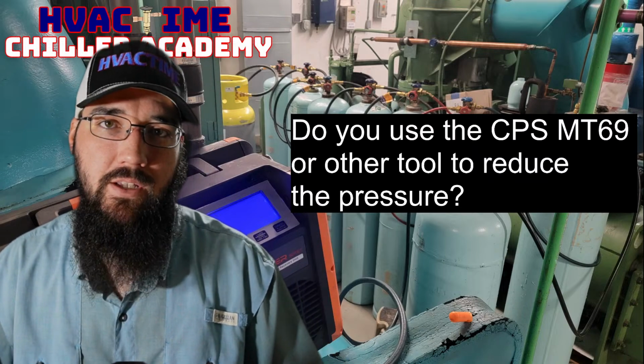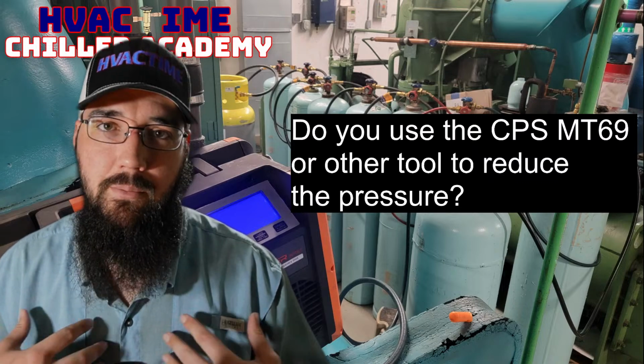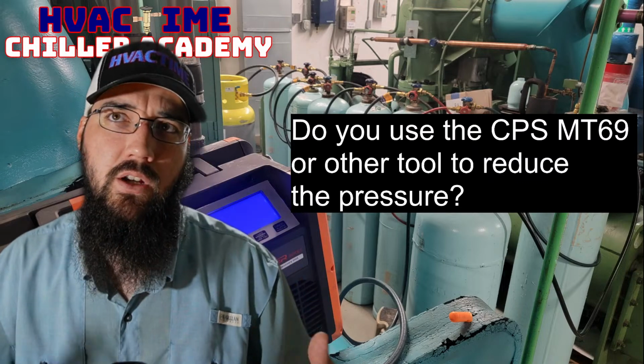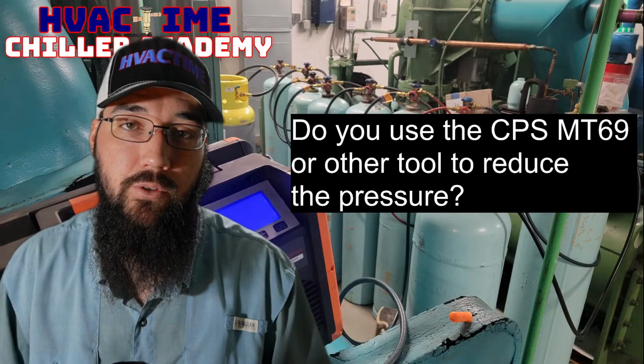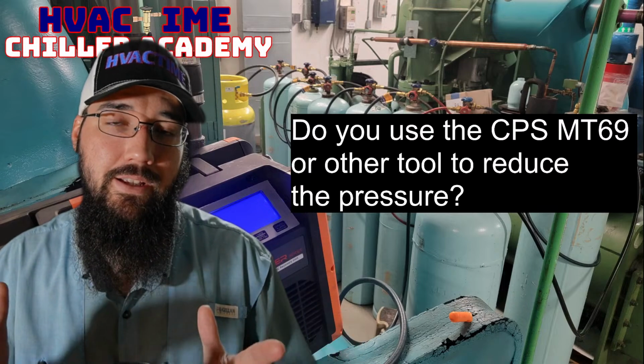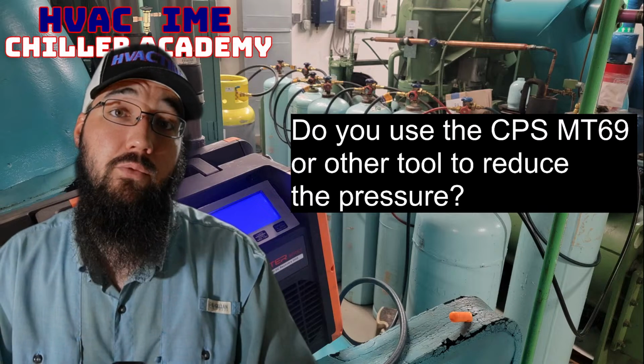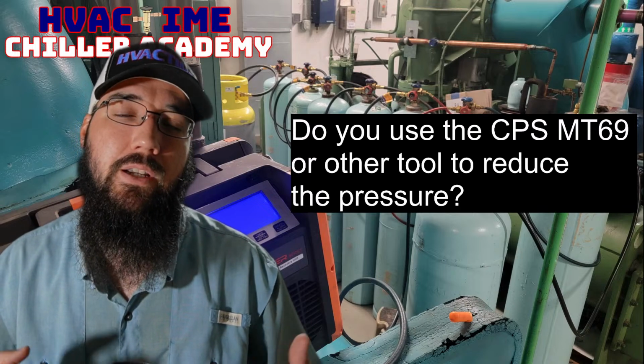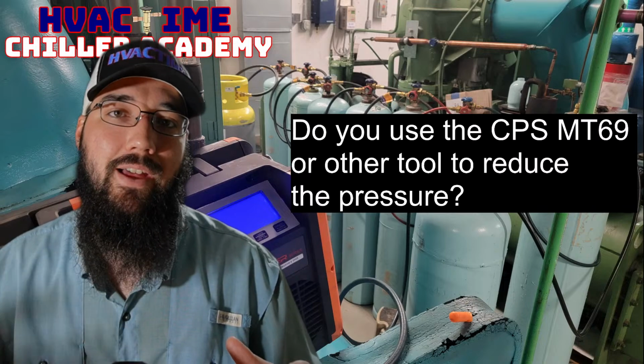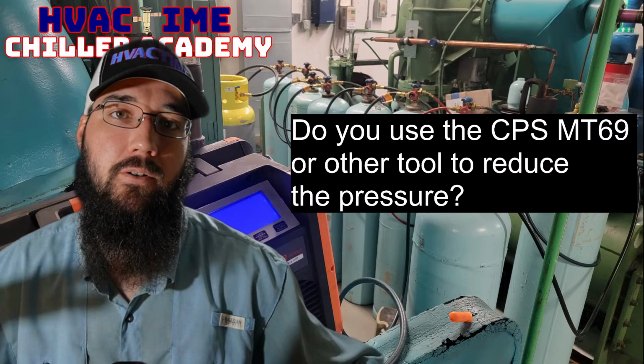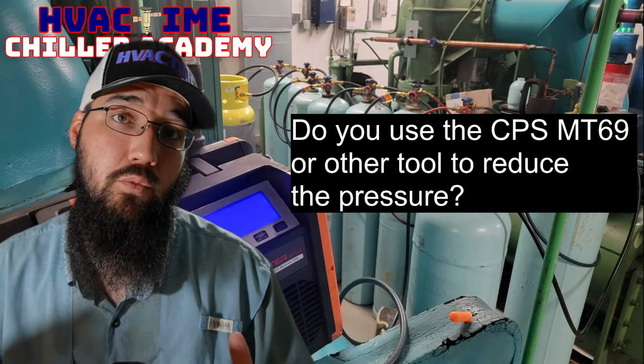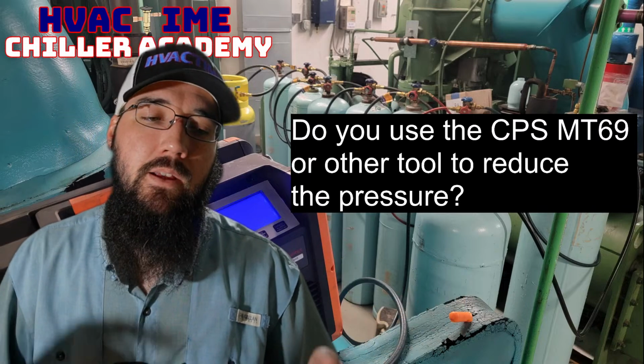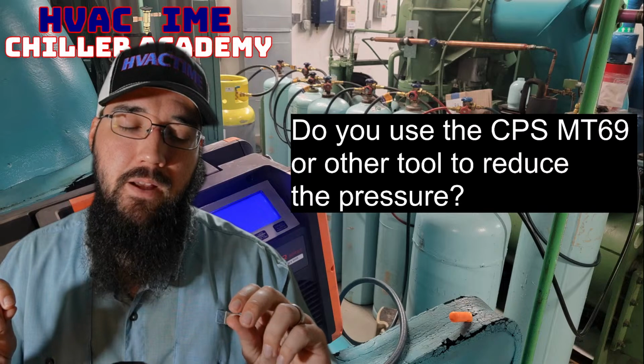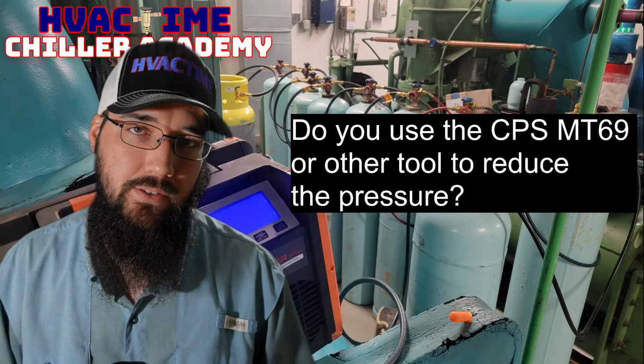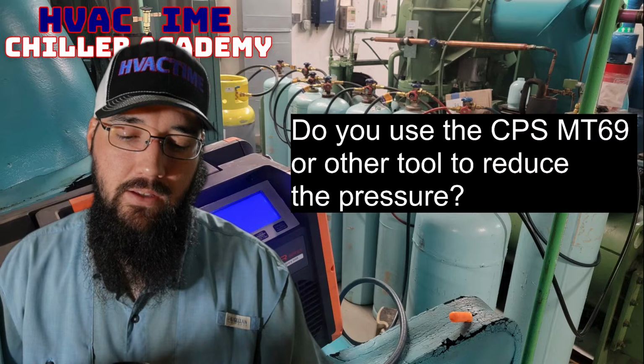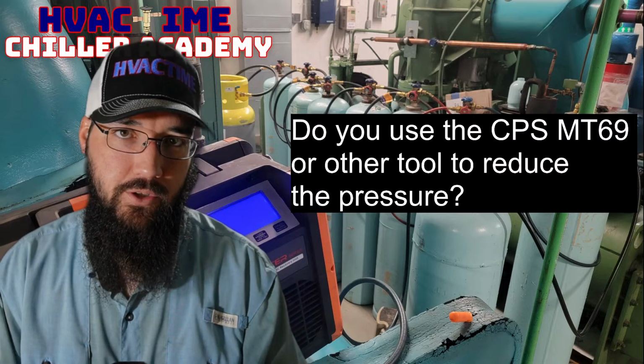So people over time have used water hoses on the tanks. I mean, I've done that plenty of times. There's several methods we've tried to use. So a subcooler is an extremely effective way of being able to de-superheat that refrigerant, so that we don't allow that heat to stack on our cylinder, and we keep our tank pressure down, which means we move more refrigerant faster. So my issue with CPS's design is moving large volumes in a chiller application.